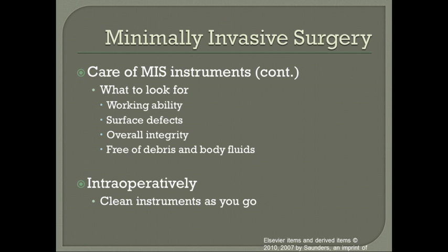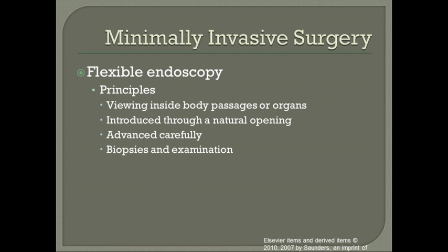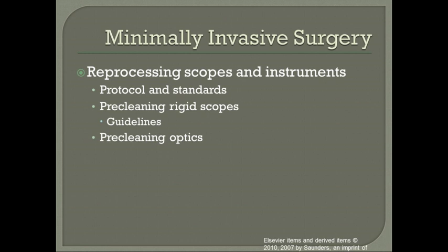And then flexible endoscopy is for viewing inside a body passage or organ. It's introduced through a natural opening and advanced carefully, such as in a colonoscopy. It's used for biopsies and examinations. Since the endoscope and instruments often come into contact with areas of the body that contain a high level of bioburden, a systematic cleaning process is necessary to ensure patient safety. And the hospital policy for reprocessing endoscopes follows the Occupational Safety and Health Administration guidelines.